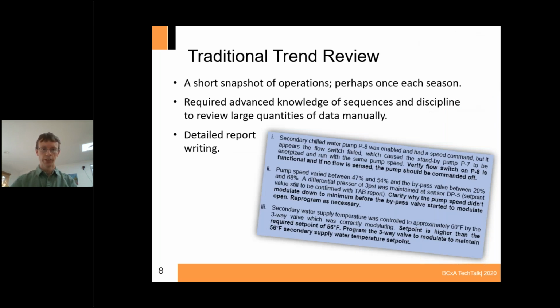The traditional trend review was really just a snapshot of operations. That's the way I learned it. We did it at substantial completion, and then again in the opposite season, just for a 24-hour period at hourly intervals. Not a lot of data, but enough to get a good comfort feeling before going into the building to do performance verification, and to identify major issues that needed to be resolved before we stepped foot in the building.